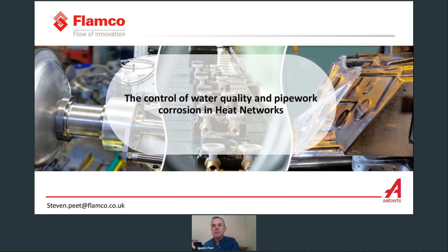There's some excellent guidance, standards and best practice available. There's BG 50 2021, which has just been revised, and that advises on the water treatment program post pre-commissioning and cleaning of systems. It refers to pre-treatment of fill water, removal of dissolved gases, chemical water treatment, pH management, solids removal and filtration, as well as bacterium and biofouling inhibition by biocides.